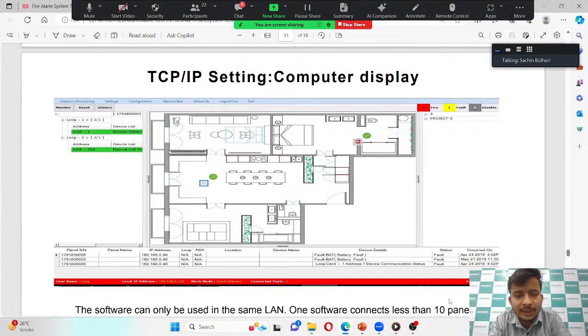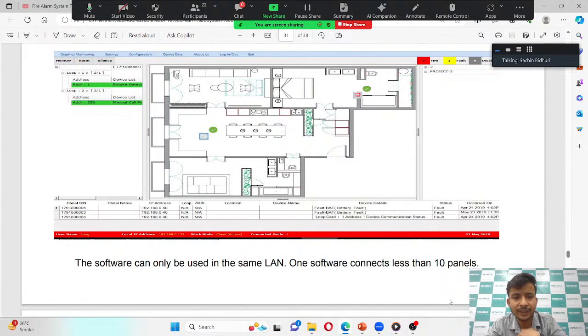Then for connecting the software, you need to give the panel the same LAN as your network. Like if you are connecting your laptop with the panel, you need to give the same VLAN. If your laptop IP series is 192.168.1.something, then you need to provide the same IP range to the panel. Or if the panel IP address is 192.168.something, then you need to give the same range to your laptop for connecting the software with the panel. One software can be connected to up to 10 panels or fewer.